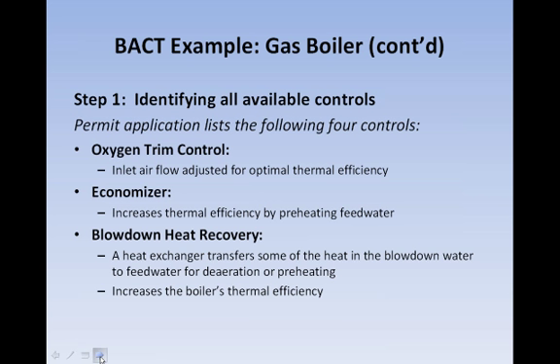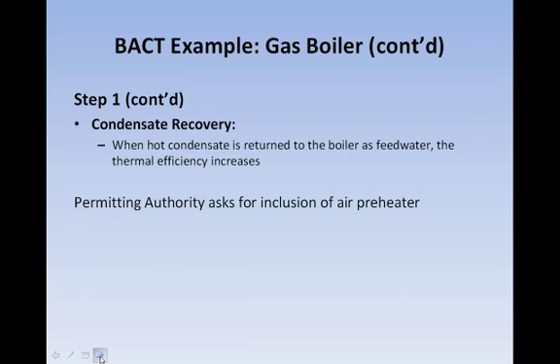For step 1, we would again identify all available controls for this proposed source. In this case, we have oxygen trim control, an economizer, blow-down heat recovery, and also condensate recovery. The permitting authority asked the applicant to expand the analysis to consider an air preheater, which is a heat exchanger which recovers heat in the exhaust to preheat combustion air. Accordingly, the permit applicant and the permitting authority agreed to include this, and so we have 5 control measures that were considered available under step 1.